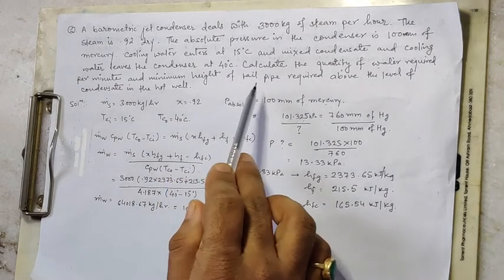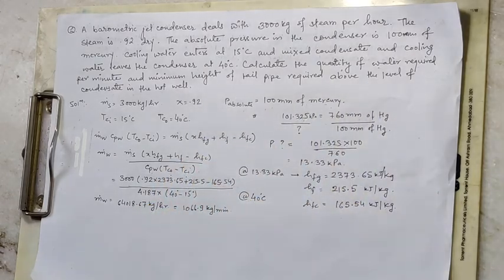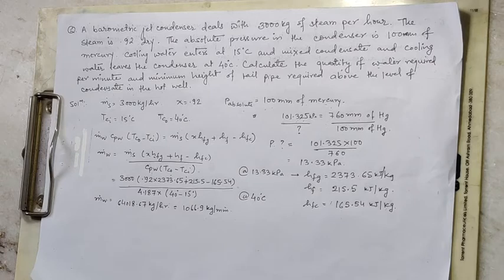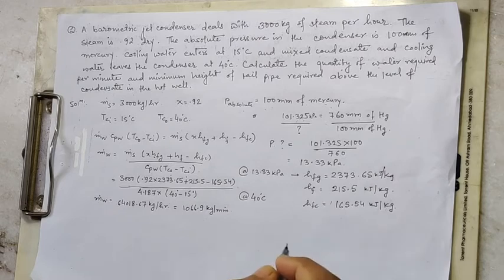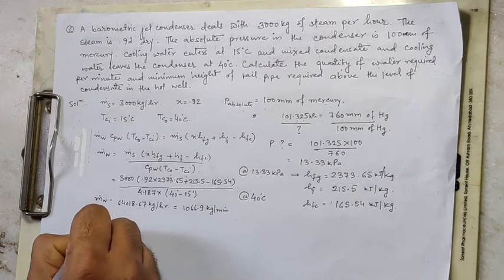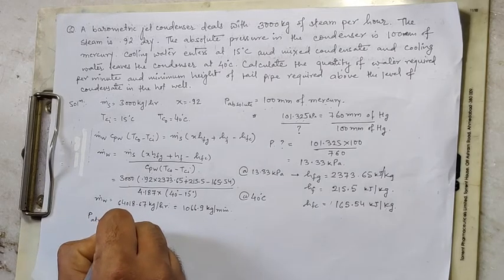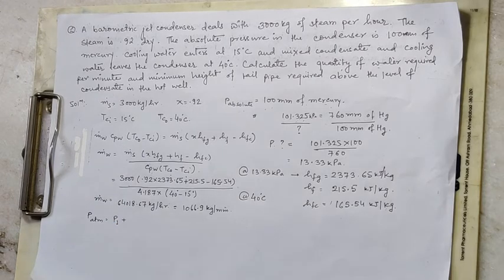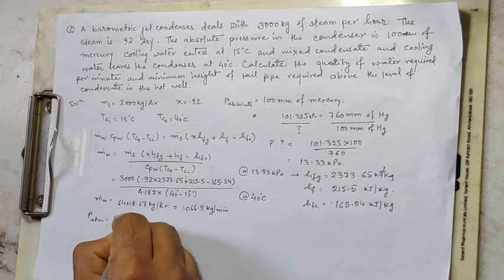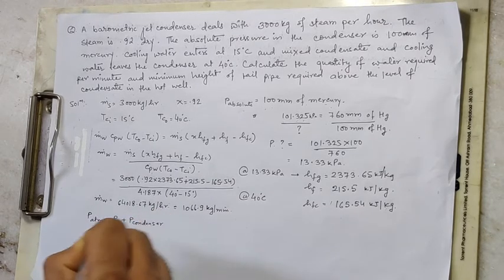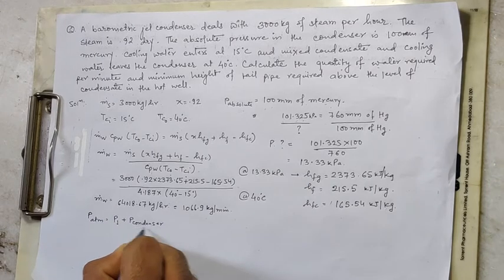Now for the minimum height of the tail pipe: the pressure in the hot well is atmospheric. That atmospheric pressure equals the sum of the pressure in the tail pipe (P1) and the condenser pressure. So: P_atm = P1 + P_condenser.